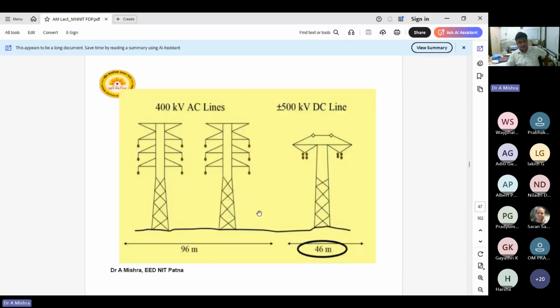Here, for the example, you see the two types of transmission lines. First one is the 400 kV AC line. Second one is the 500 kV DC line. So this is about the tower size and the area it is taking. If you are in agricultural land and open area, then space may not be a problem. But if the same thing is passing through the urban area, then space will be an issue in certain cases.